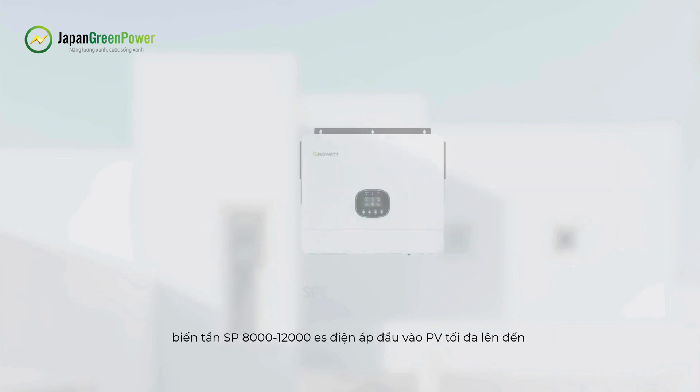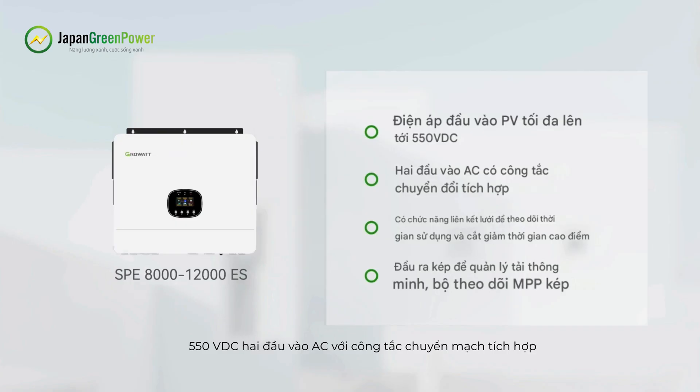The Growatt SPE-8000-12000ES series hybrid inverter can use Wi-Fi or 4G device for remote monitoring. Key features include maximum PV input voltage up to 550VDC, two AC input terminals with integrated transfer switch featuring grid-tie function for time-of-use and peak shaving, dual outputs for smart load management, and dual MPP trackers.